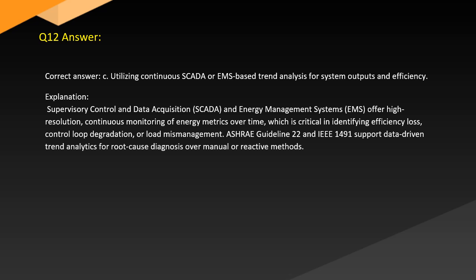Answer. Correct answer. C. Utilizing continuous SCADA or EMS-based trend analysis for system outputs and efficiency. Explanation. Supervisory control and data acquisition (SCADA) and energy management systems (EMS) offer high resolution continuous monitoring of energy metrics over time, which is critical in identifying efficiency loss, control loop degradation, or load mismanagement. ASHRAE Guideline 22 and IEEE 1491 support data-driven trend analytics for root cause diagnosis over manual or reactive methods.